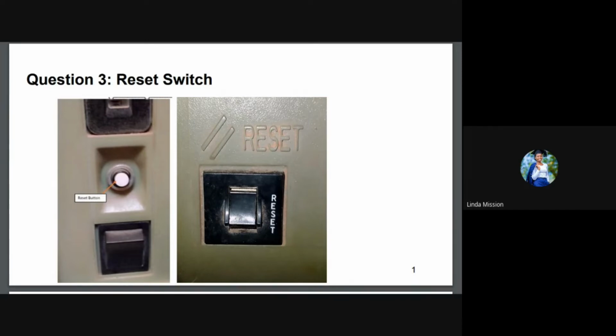If all of the above mentioned seem to be okay, then you have to check the PCB's electrical integrity by disconnecting the mains power and removing the control board from the concentrator. Then you have to look for any short circuits on the control board using a digital multimeter. So if all the above mentioned suggestions check out, you have to check the reset button's electrical integrity as well, by replacing it with a working reset switch and check if the problem persists or not. So the images in the graphics are just showing the reset buttons which you are going to find in different concentrator models. Thank you, Maui.